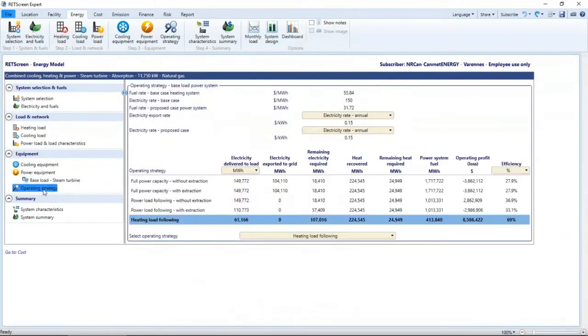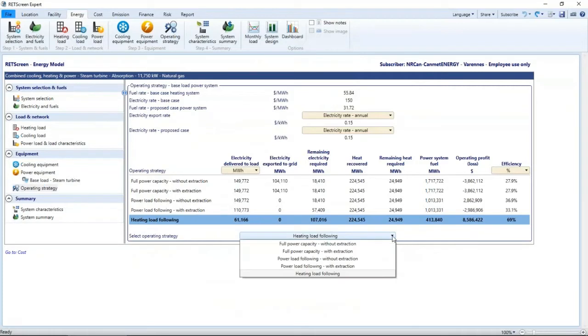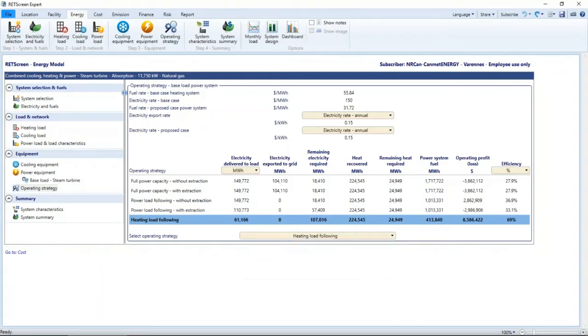Now, let's see what operating strategy could offer in this case. There is a possibility to choose between 3 operating approaches: full capacity output, power load following, and heating load following. Taking advantage of the extraction port is also an option. However, I see that the system cannot benefit from the extraction port to provide more heating capacity. I came to that conclusion because the heat recovered column is equal for all cases.